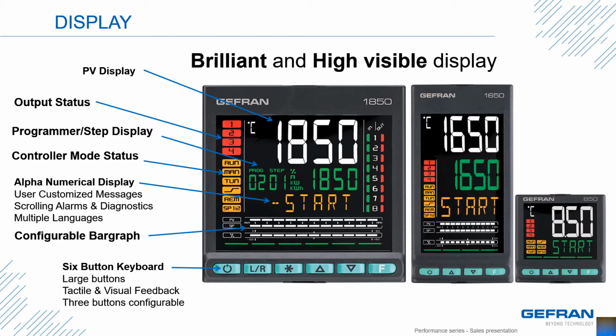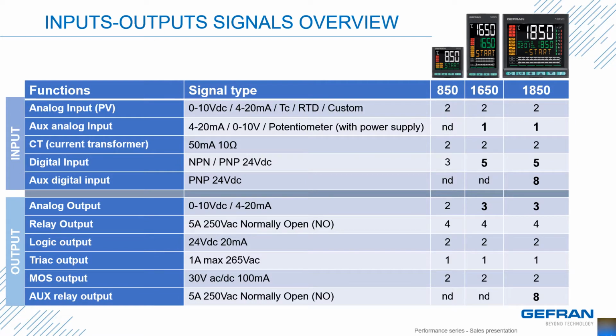As we move to the 1/16 DIN 850, we lose a little more of the display features like the third line and the bar graph, but keep in mind, one of my favorites, the tactile and visual keypad feedback is still there. For the inputs and outputs, we have a wide range available. In the model codes, you'll specify which ones you'll need for your applications. How many are available depends on the size of your instrument, with the 1850 having the most.